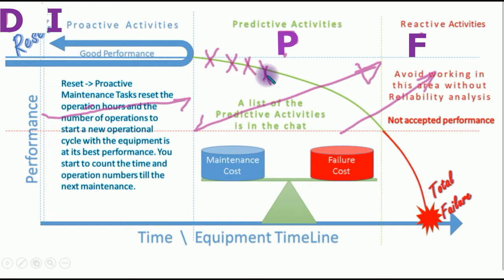You have some equipment that is totally stable — nothing is happening to it. You stop every now and then to make some retightening, some visual inspection, because you cannot come to close proximity of these parts while they are in operation. But sometimes, when some looseness happens, when some little sparks happen, some deterioration in the quality of a capacitor, bolt, or something like that, you start to have some heating of one part relative to the other parts. That's the beauty of thermography.